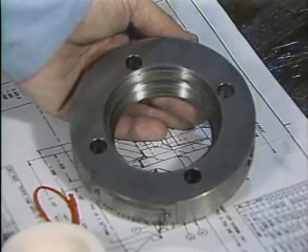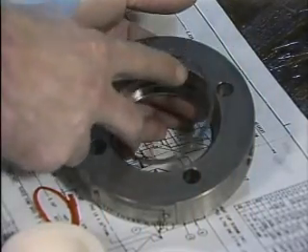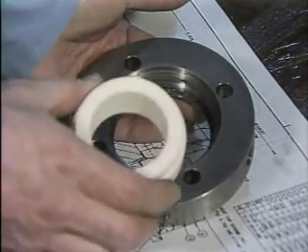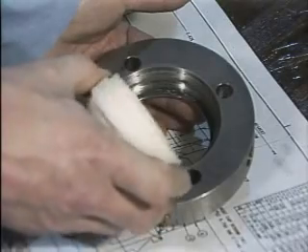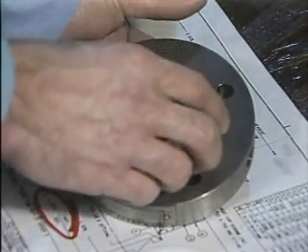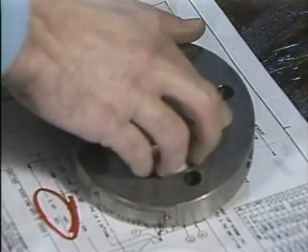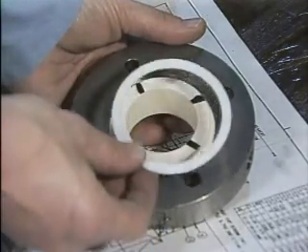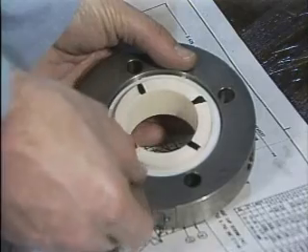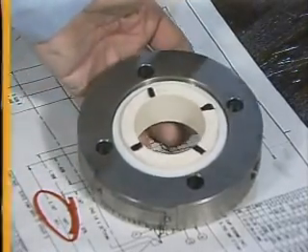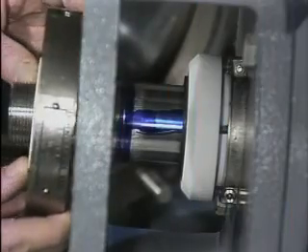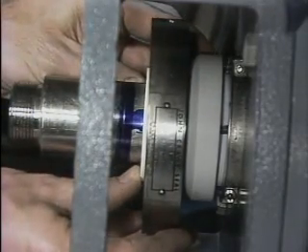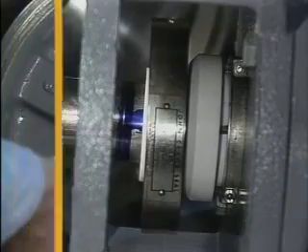Then the stationary element is prepared for installation. A gasket is placed in the gland plate. Then the mating ring is installed. On an outside seal, the polished side of the mating ring is installed so that it faces away from the stuffing box. Then a second gasket is installed, and the gland plate assembly is ready to be mounted onto the shaft. The gland plate should be slid back on the shaft as far as possible and positioned against the rotating element that was just installed.